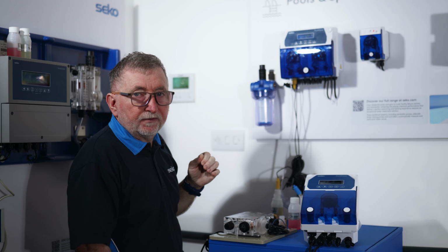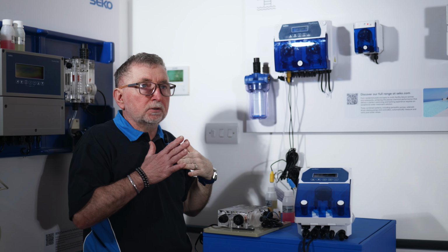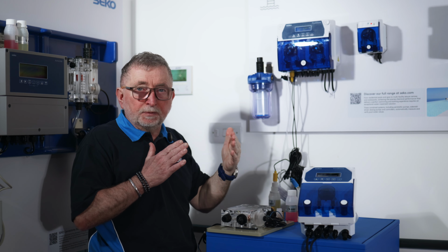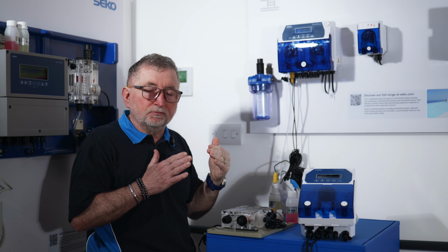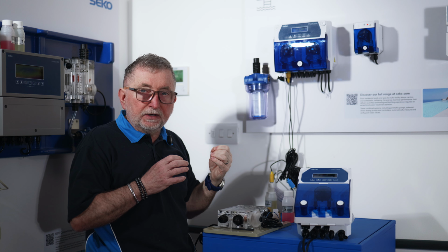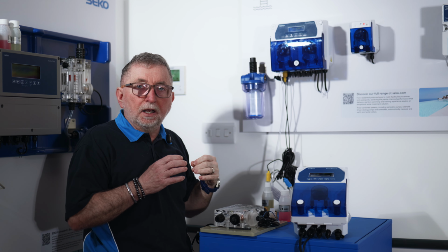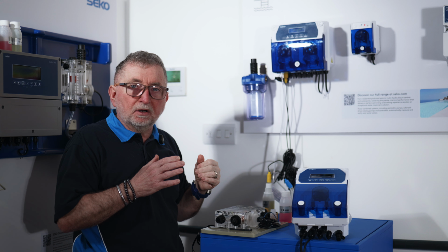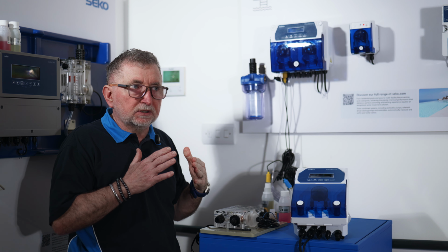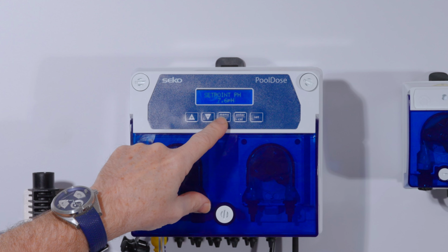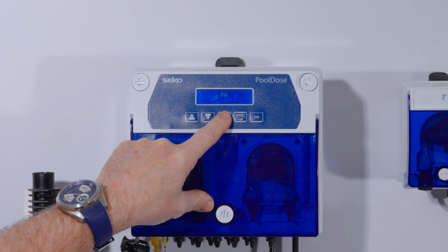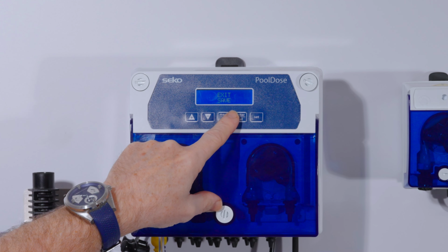The purpose of the OFA alarm is to stop the system if it's been dosing for a certain period of time and hasn't reached its set point. The first time, OFA 1, it will just alarm. The second time, it will detect a significant problem and will stop the dosing. We're now back to set point, and again, if we escape out the menu, and if we want, save our changes.